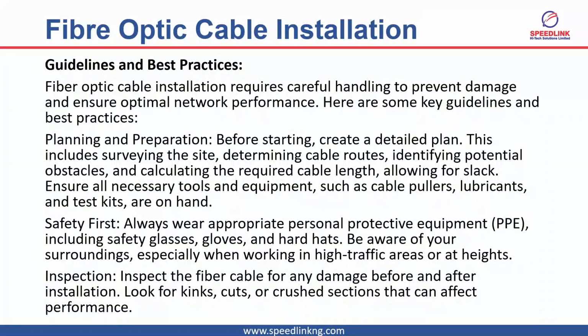Now, if I measured 600 meters, what is a good amount of slack that I can add? First, where you're going to terminate the cable, there are some lengths of the cable you would use for termination purposes, isn't it? As you terminate here, you also terminate over there. Let's estimate, okay, 10 meters here, 10 meters there. That means how many meters altogether? 20, isn't it?